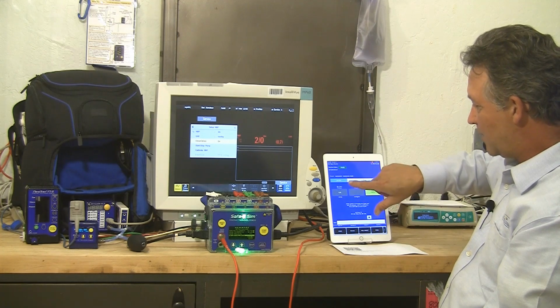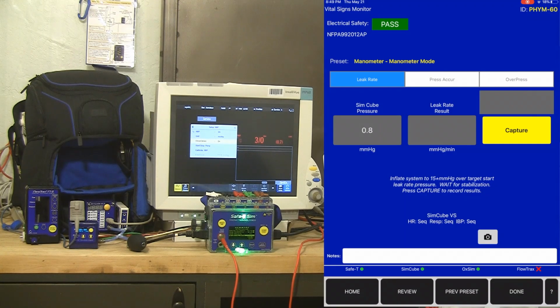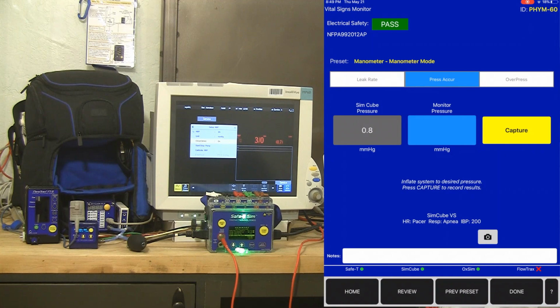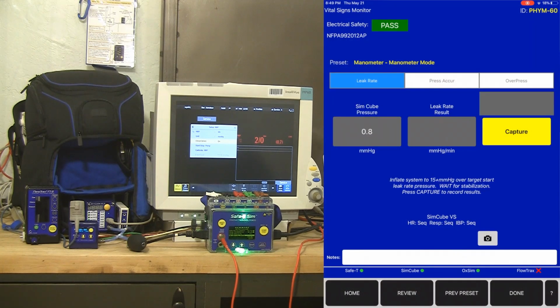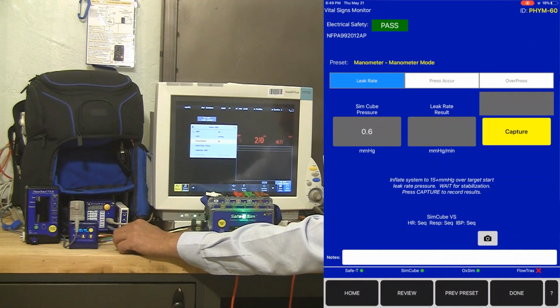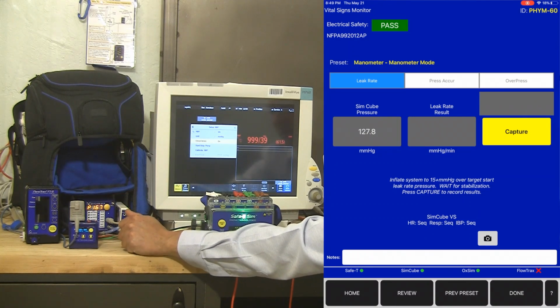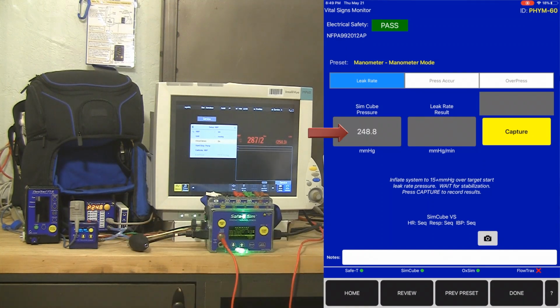From our app, we've got three different selections in manometer mode. We've got leak rate, pressure accuracy, and overpressure. We're going to start with a leak rate. So I'm going to inflate the system to about 240, and I can see on my app that it is tracking the pressure of the sim cube. Here's about 240. And so I can see my real-time sim cube pressure right on my iOS device, and it's going to start calculating a leak rate.